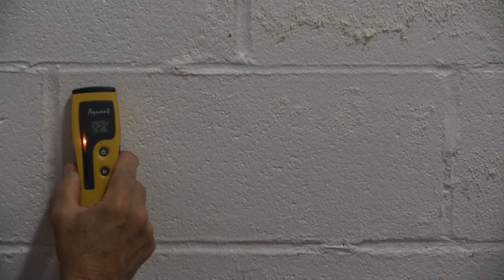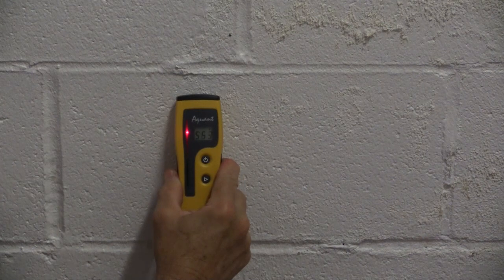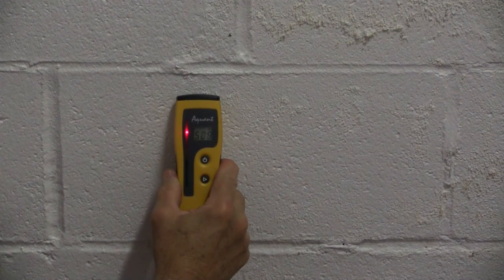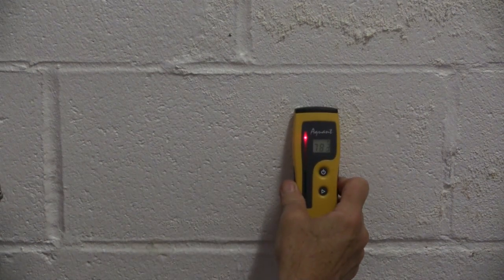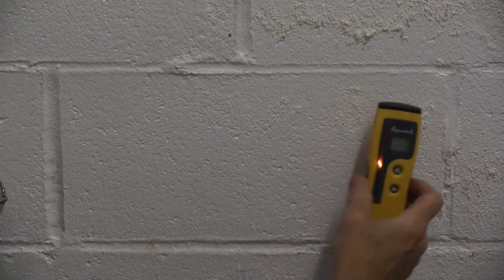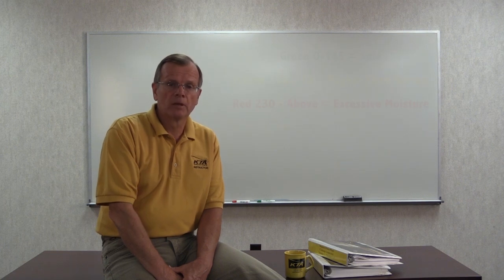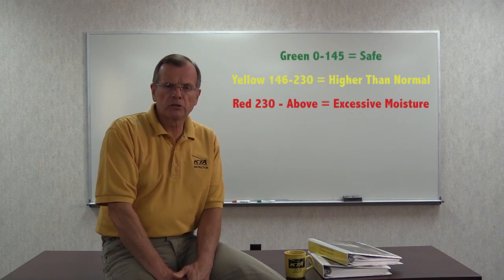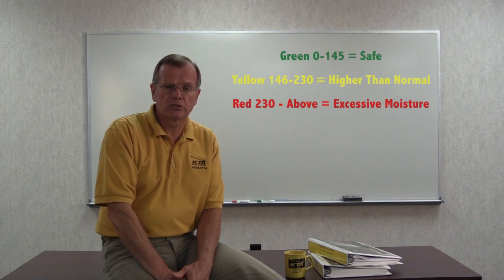Another moisture meter is based on radio frequency. This instrument utilizes radio frequency to assess and monitor the relative moisture level in porous materials such as concrete. The instrument from one manufacturer provides readings on a relative scale from 0 to 999. The instrument displays the results using both a color and a number.